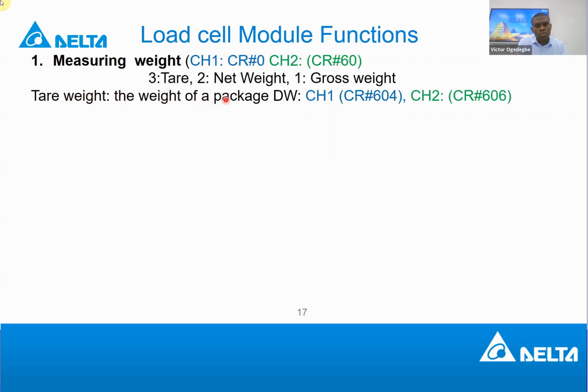What is the tare weight? The tare weight is the weight of a package. So in the case of the bucket, the tare weight is the weight of the bucket. You can get the tare weight value in this register. So you see, it's very easy and handy to control your load cell, the weight you are measuring using this load cell module, because you have access to each data in a specific register. This register is a double word 32-bit register. You can see the tare weight.